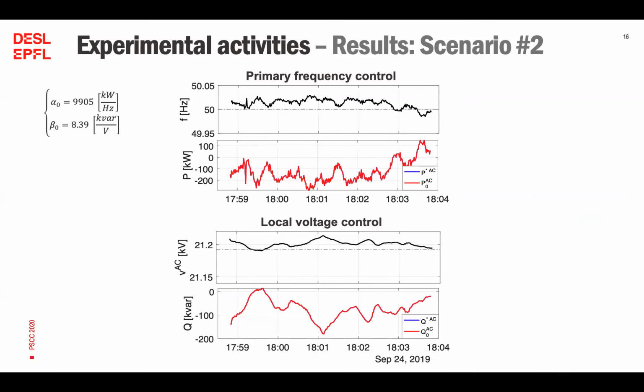So the first set of results is for scenario 2, and the droop values are the ones reported on the left. In the top plots, you can see the frequency measured during the test period and the corresponding calculated initial and final active power in red and blue respectively. Actually, only the red line is visible because the two are overlapping. And this is due to the fact that we don't have such a big frequency deviation, meaning that the initial set point is already inside the feasible region.